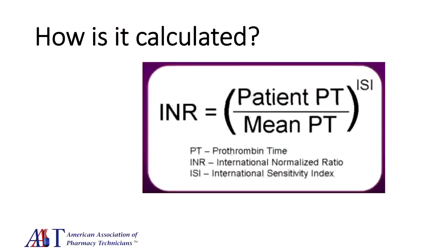Fascinating, right? And then your analyzer will just take that prothrombin time and calculate what the INR is using this formula. So it's basically your patient's prothrombin time divided by a mean normal control. The mean normal control is like once a year you would take samples from 30 people who are not on blood thinners, and you just average whatever that prothrombin time is, and then you would enter that into your analyzer to use that calculation.